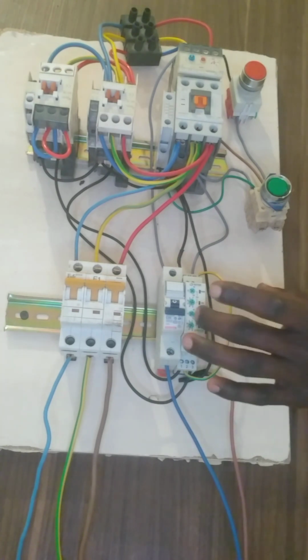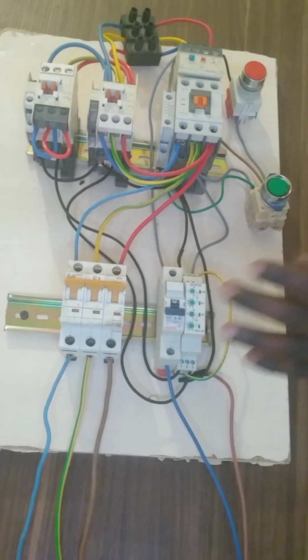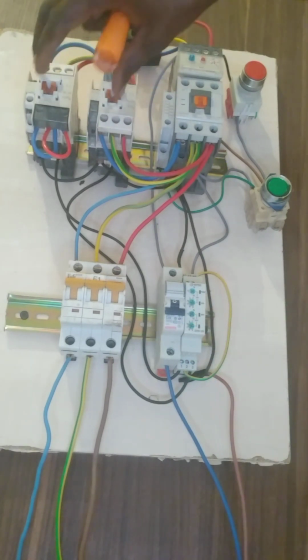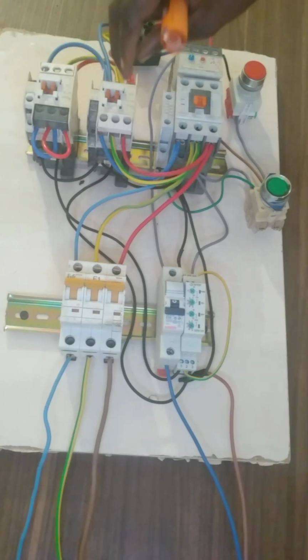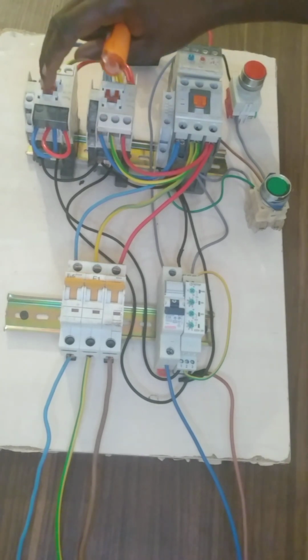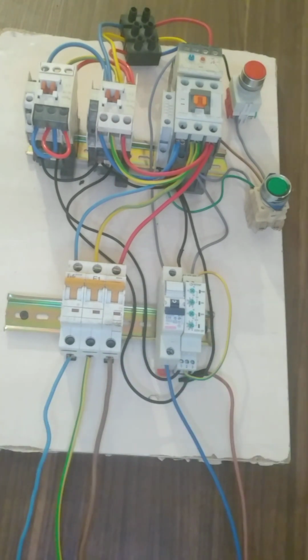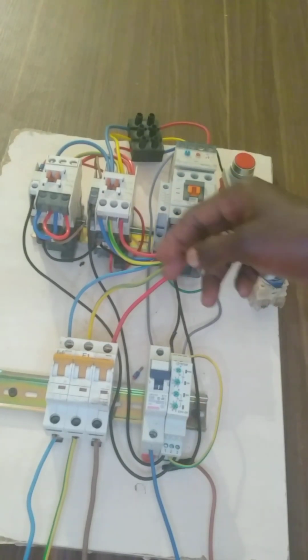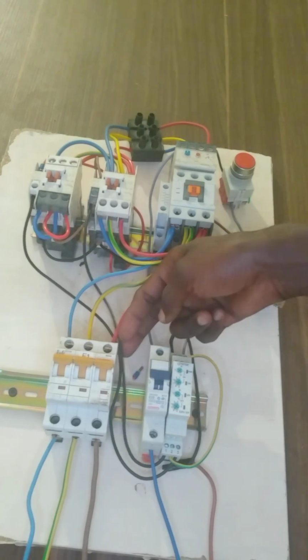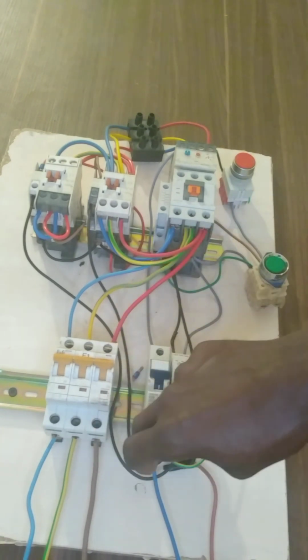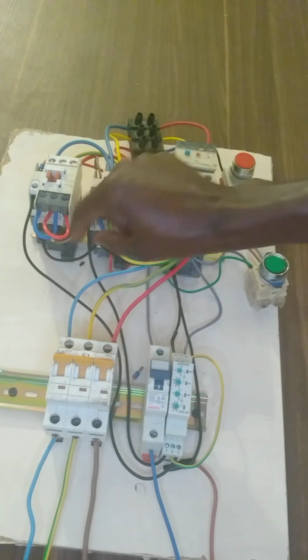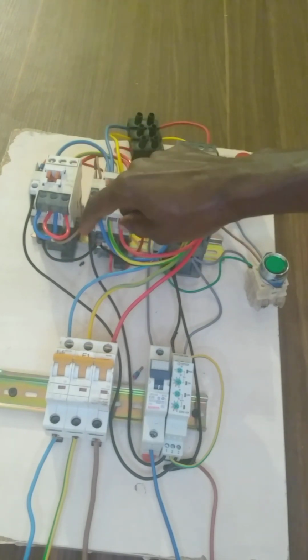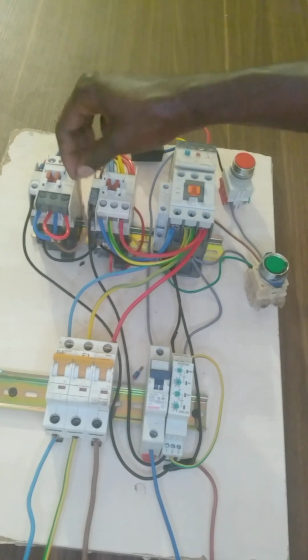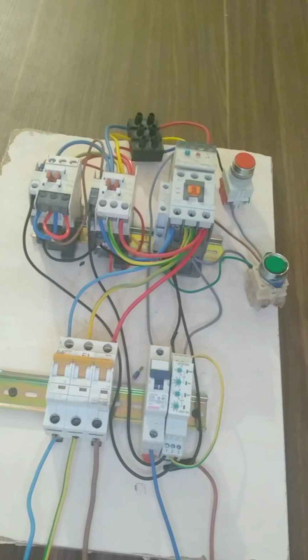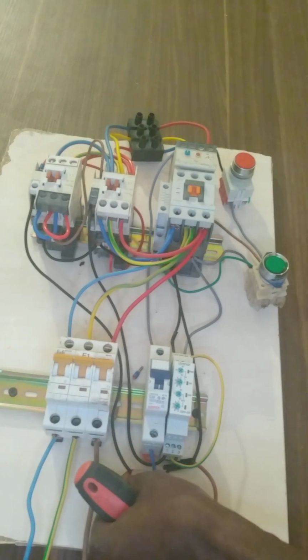If there is a problem in the timer, the contactors will not go at the same time. If this one goes on, that one stops. Now I am going to make the electrical interlock. As you see, I do the electrical interlock from number 1. Before I go to the A2, I connect to the normally closed contact of this delta contactor. Then I return back to the A2 of the star contactor. The same thing for the star.